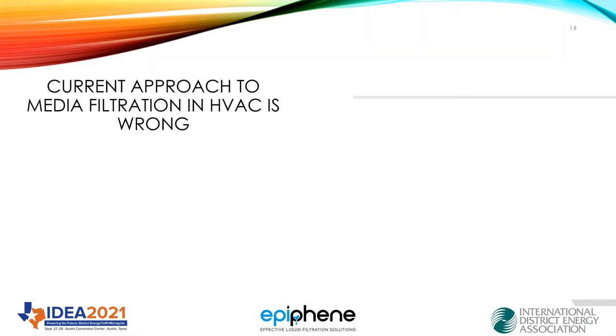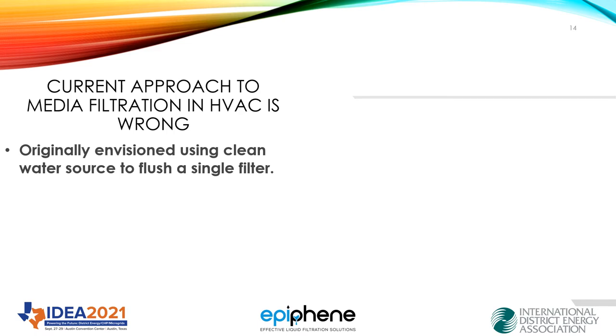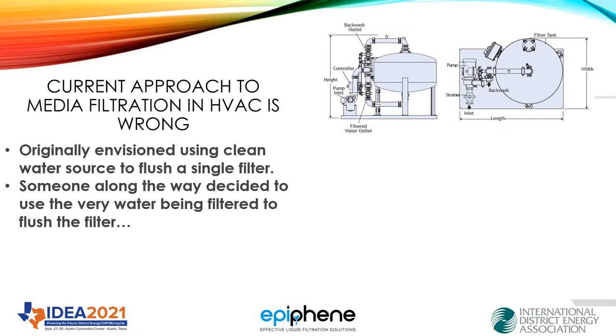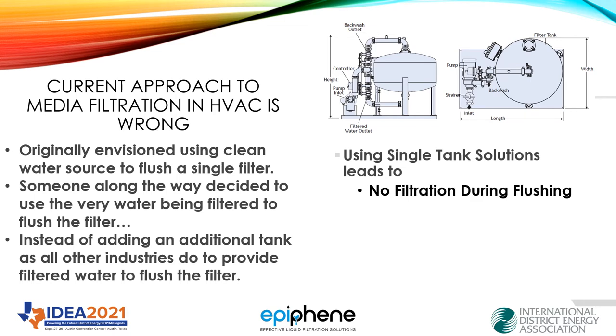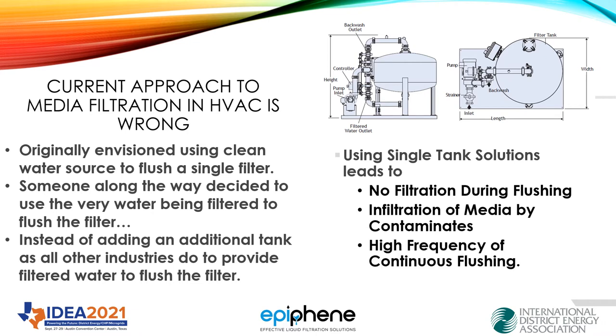I want to talk briefly about why I believe the current approach to media filtration in HVAC is wrong. First, it was originally envisioned using a clean water source to a single filter. Somewhere along the way, somebody decided they could use the cooling tower water to flush the filter — instead of adding an additional tank, as all other industries do, to provide filtered water to flush the filter. So these single tank solutions basically provide no filtration during flushing. The infiltration of the media by contaminants from using dirty water to fluidize the bed is a no-no, and it actually leads to high-frequency or continuous flushing. Eventually that system is abandoned because it fails — either from surface sealing issues, contamination of the bed — and the bottom line is that filter gets taken out of service.